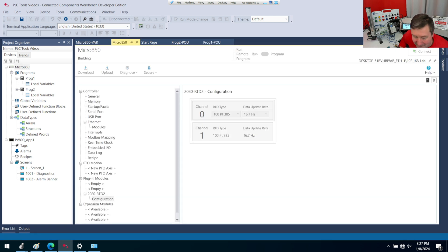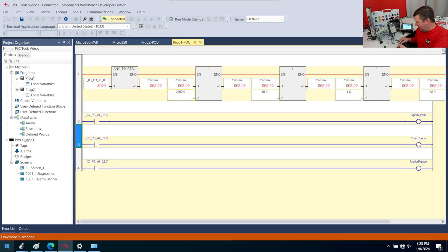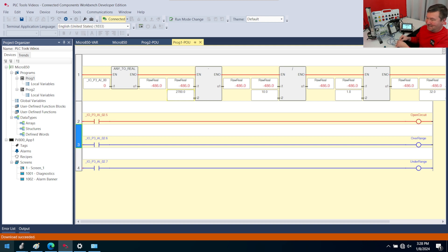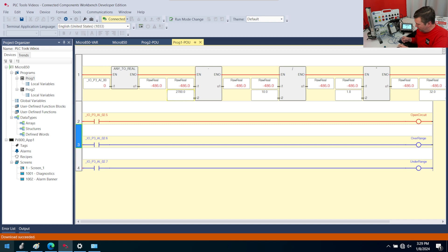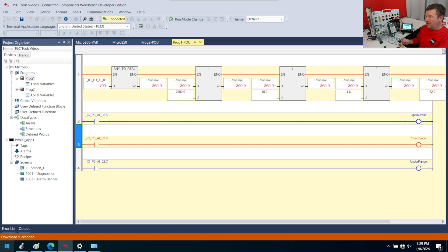Now if I disconnect our RTD simulator, we get an open circuit. And if I put it back on, it closes. Now I believe I can short out the two wires from the plug-in module and I should get an overrange — and there you go. So now we have an overrange.